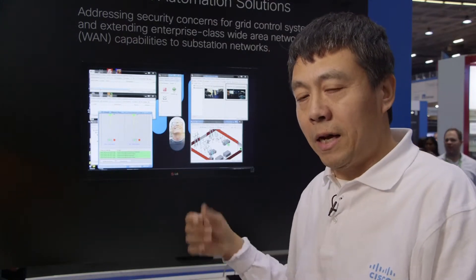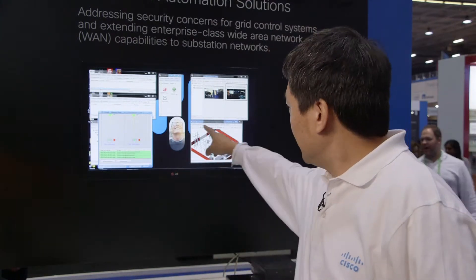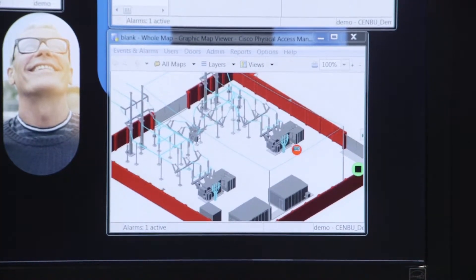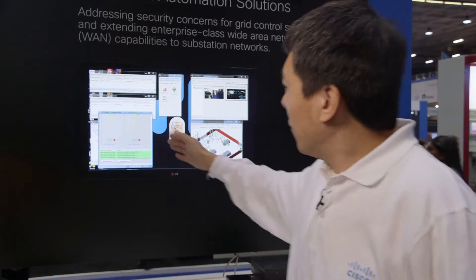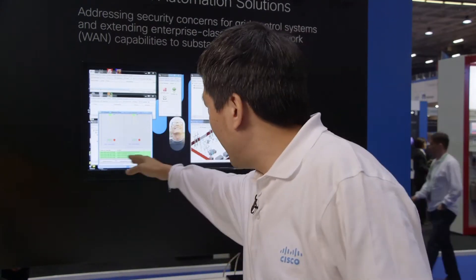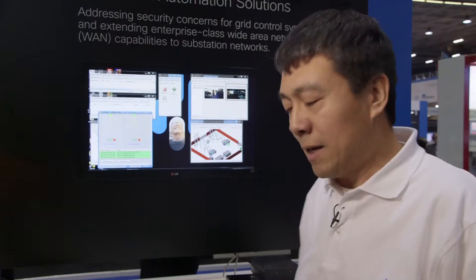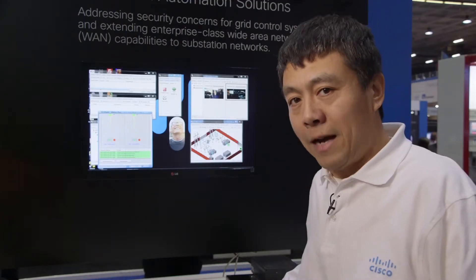What you have on the screen is a typical substation setup including the primary equipment such as transformers and the secondary equipment such as protection devices. And on the right is an HMI which monitors the protection devices' status. So what I'm going to do next is to simulate an event using this small device.